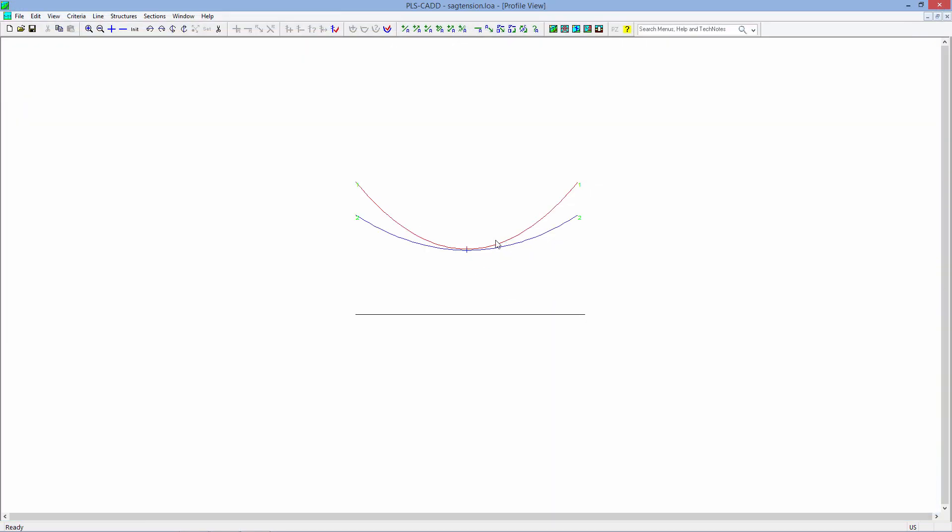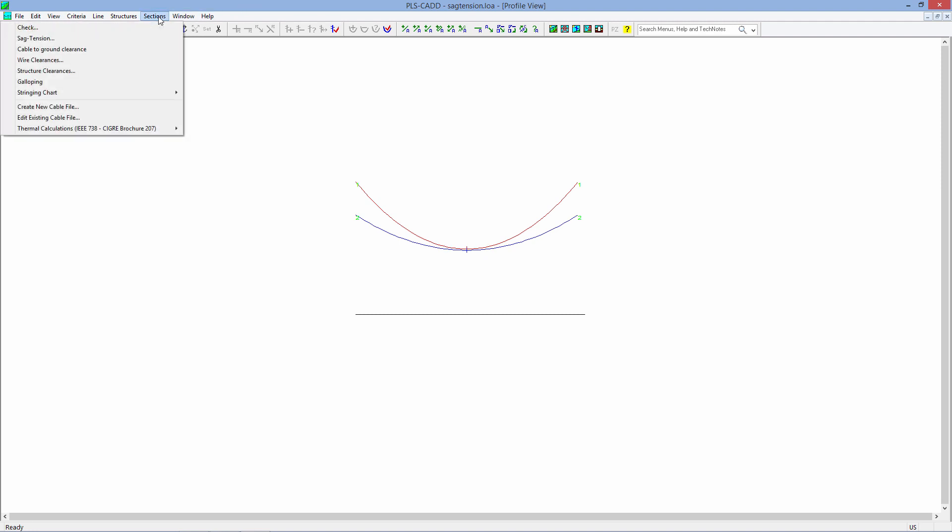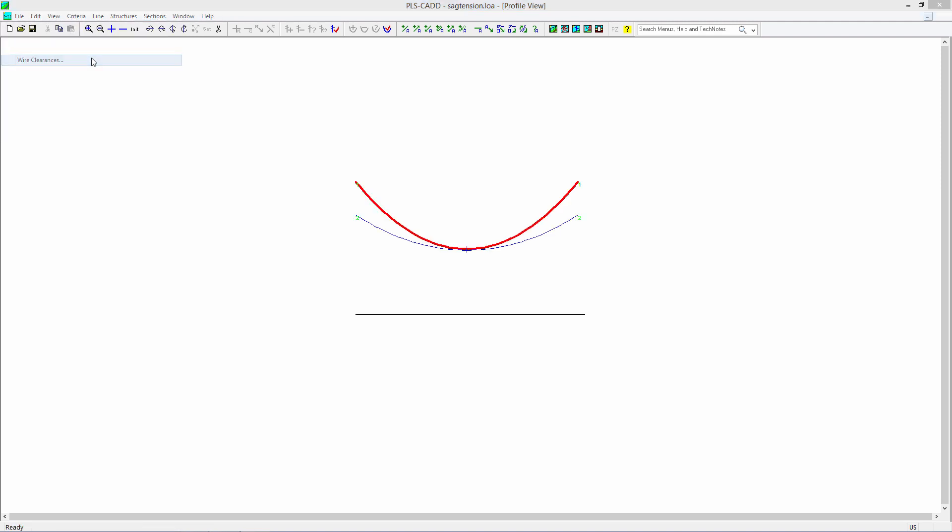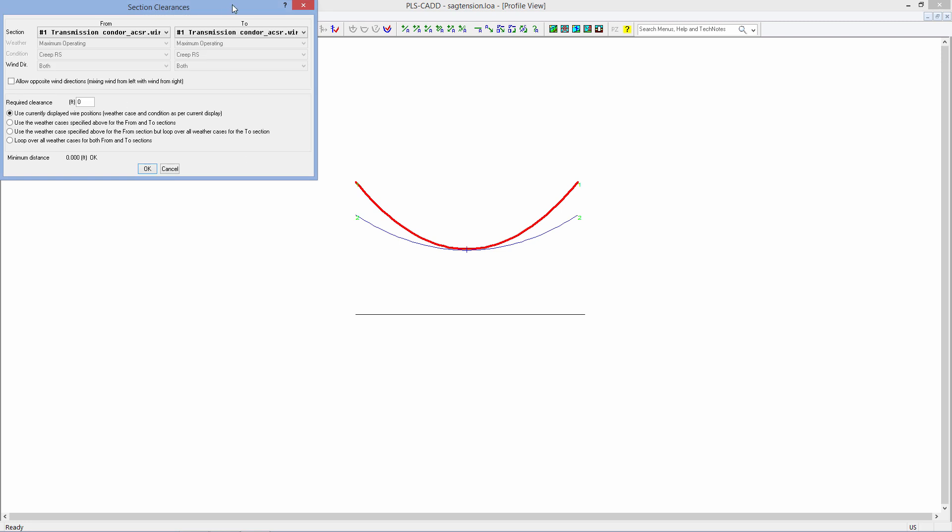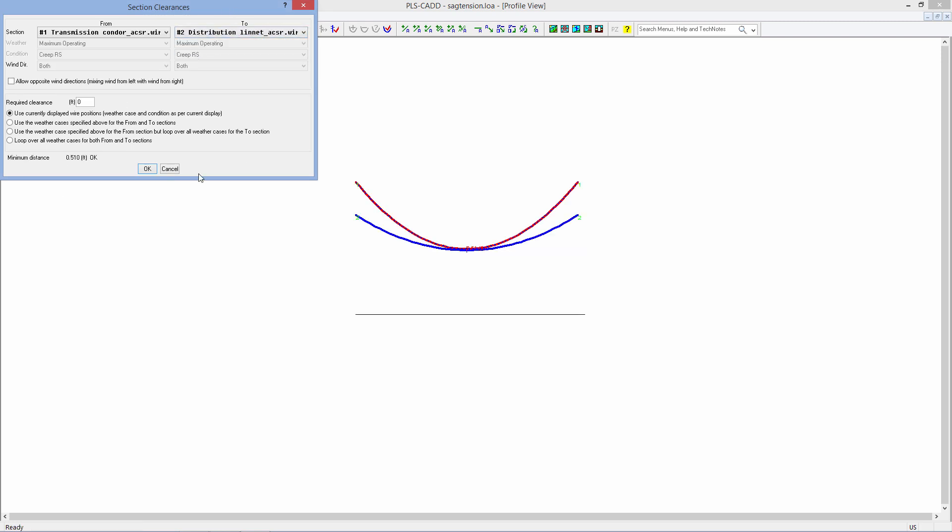But we can graphically see that we start seeing a problem between the two clearances there. We can come in here and say sections, wire clearances, and we can check between the transmission and distribution and quickly see that we have a potential for a pretty bad violation with those two wires used in that particular span length.